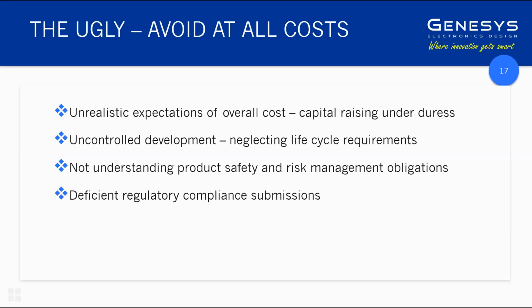And these submissions are underpinned by all of the regulatory compliance and other technical documentation that is produced during the whole development cycle of the product. So you probably get the impression from what I'm saying that these things are all intertwined and enmeshed. And if you want to be able to come up with a coherent regulatory compliance submission at the end, you have to start working on that right at the beginning.